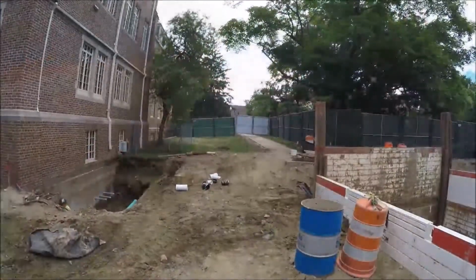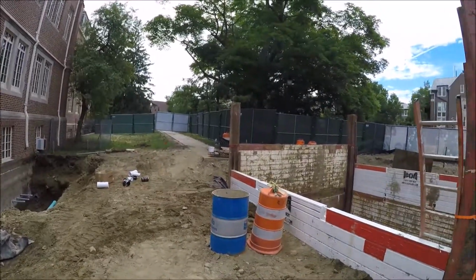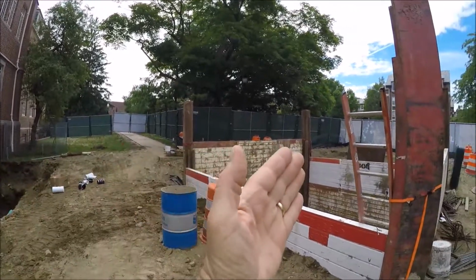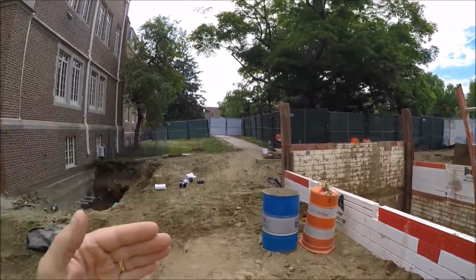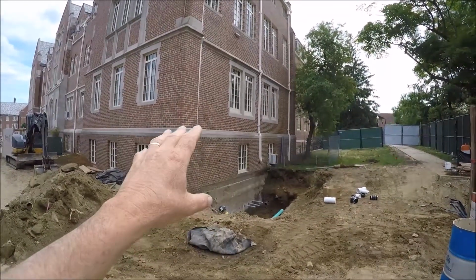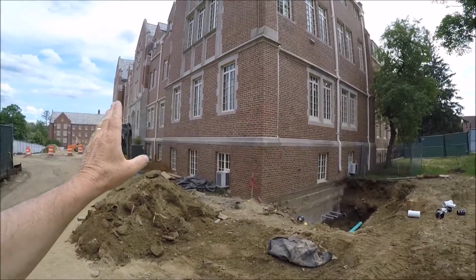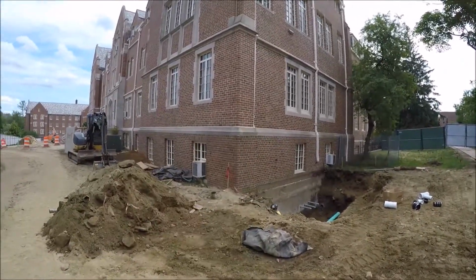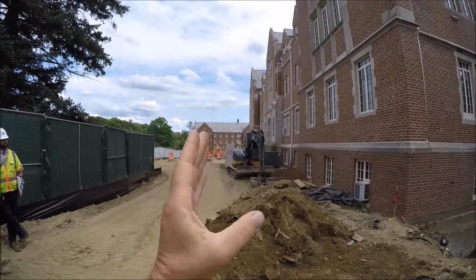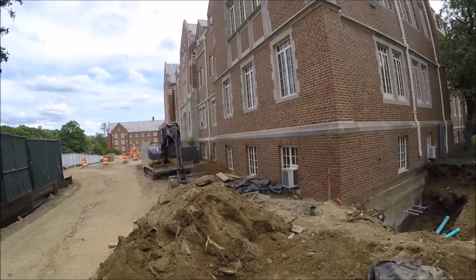In this area of the L8 vault is, again, we told you we were going to tie in. So the design here changes everything. So the new service comes this way, goes into L8, then comes out of L8, and immediately goes in. And I'm going to show you in a minute this kind of a tunnel section that runs north to south in Family Studies in here, right through there. So the big benefit is there's no longer a steam line that runs this way to Manchester. We take advantage of the inside of the building, running the pipe in through there.